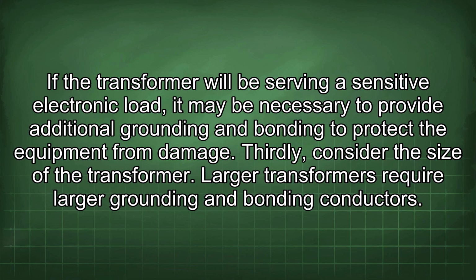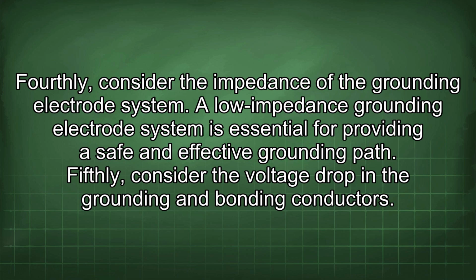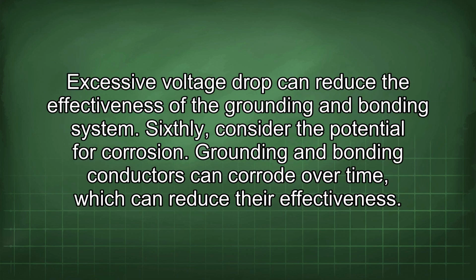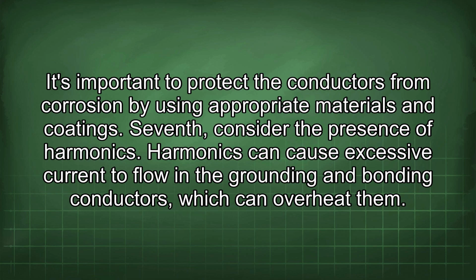Thirdly, consider the size of the transformer. Larger transformers require larger grounding and bonding conductors. Fourthly, consider the impedance of the grounding electrode system. A low impedance grounding electrode system is essential for providing a safe and effective grounding path. Fifthly, consider the voltage drop in the grounding and bonding conductors. Excessive voltage drop can reduce the effectiveness of the grounding and bonding system. Sixthly, consider the potential for corrosion. Grounding and bonding conductors can corrode over time, which can reduce their effectiveness. It's important to protect the conductors from corrosion by using appropriate materials and coatings.